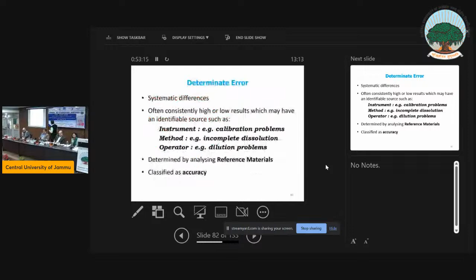Okay, I'll talk here. That instrument must be calibrated with the standards. Now, when the instrument calibration is done, you give the concentration, and the instrument only reads that and gives a numerical number, which you informed the instrument. The instrument has no sense at all. It's working on your command. If you say this is aluminium, it will read as aluminium. If you say this is 5 ppm, it will say 5 ppm. So choosing a standard and feeding a correct value is your first job.